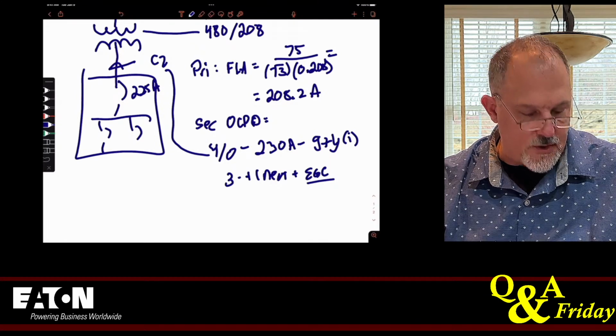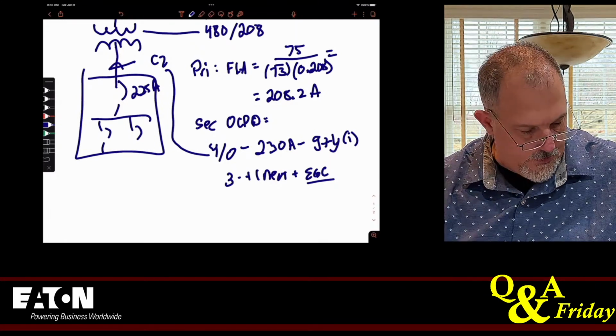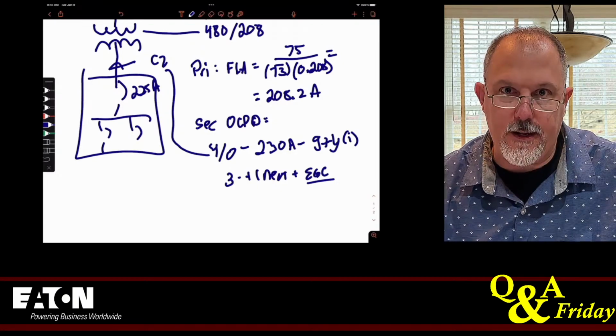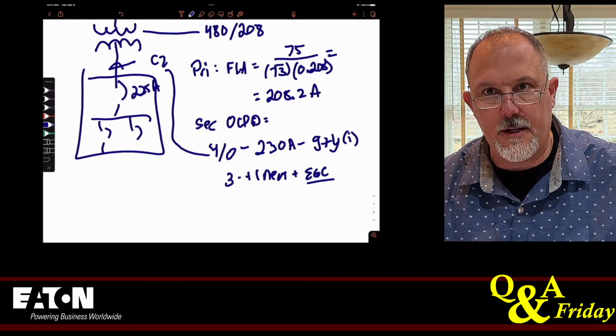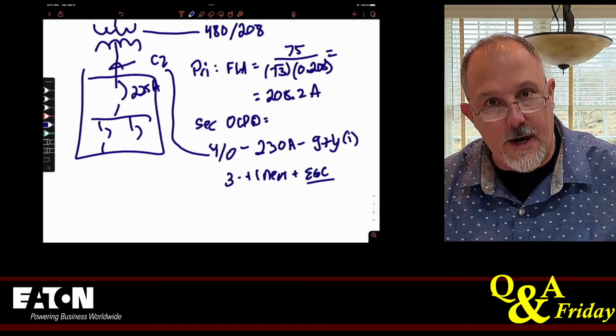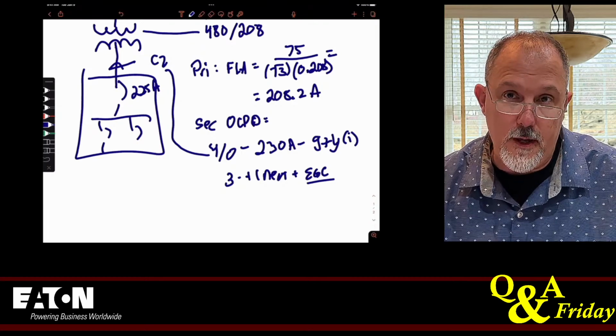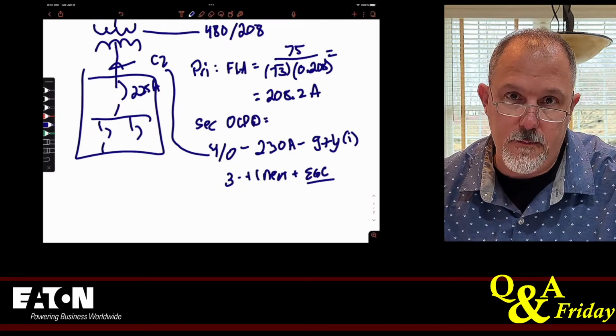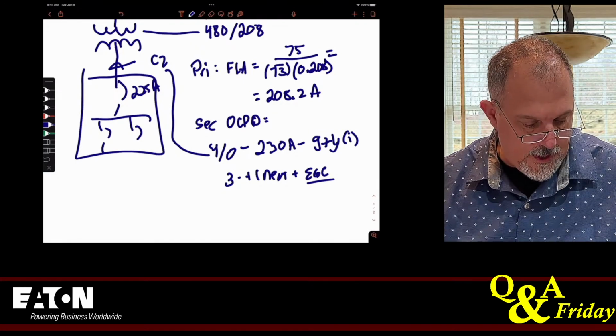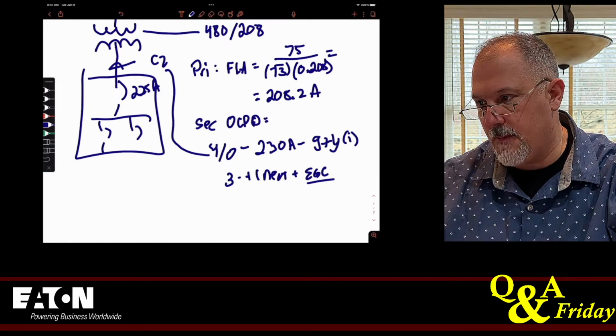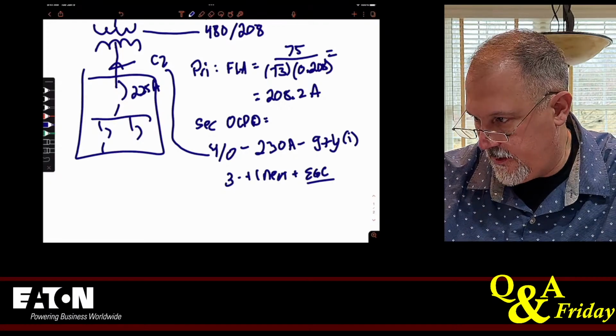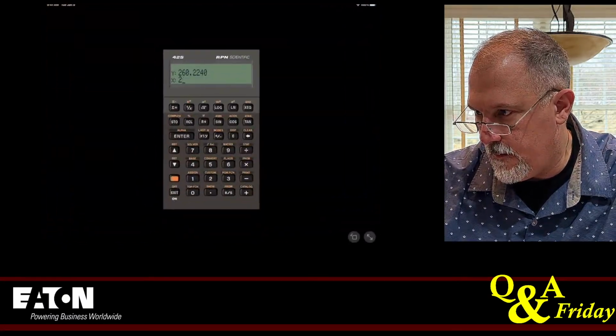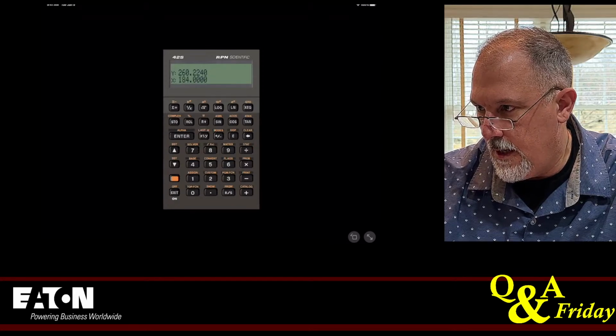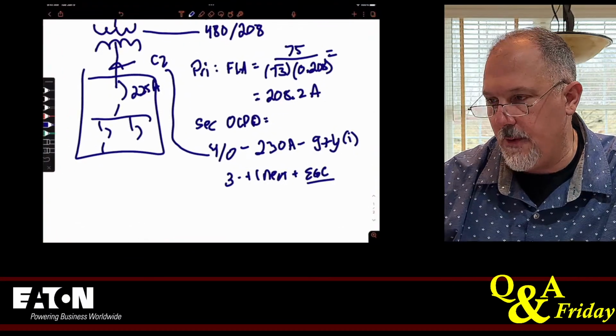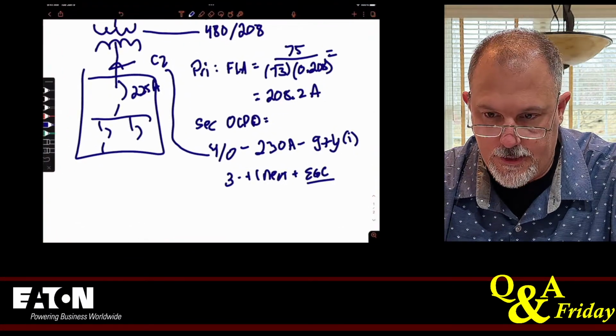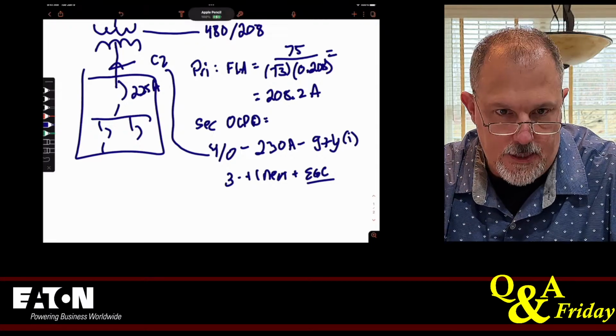Then I go to the number of conductors. 4 to 6 is 80%. I don't have to follow that because it's adjustment factors for more than 3 current carrying conductors. If my neutral is not a current carrying conductor, then I don't have to count it. But if I have unbalanced loads enough that I have to call it a current carrying conductor because I know current's going to come back over that neutral, then I would call that a 4, and I would have to go to 80% and adjust my ampacity appropriately. 230 times 0.8 is 184. I would have to add another one if I have to call that a current carrying conductor. Make sense?